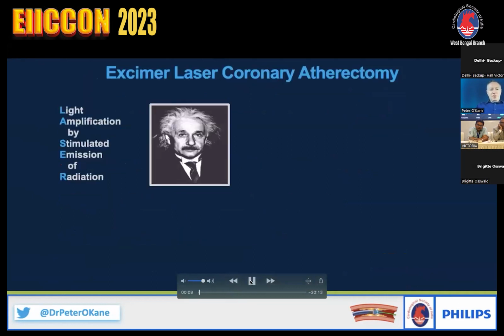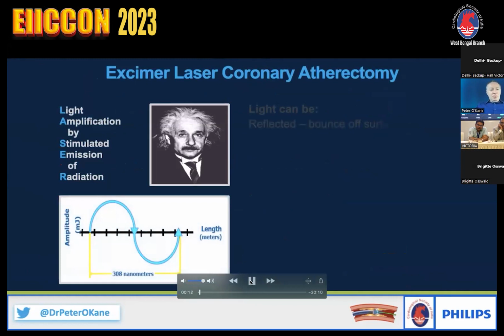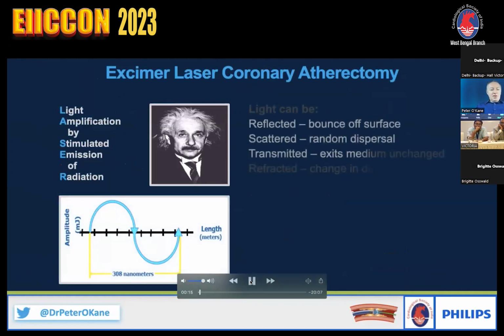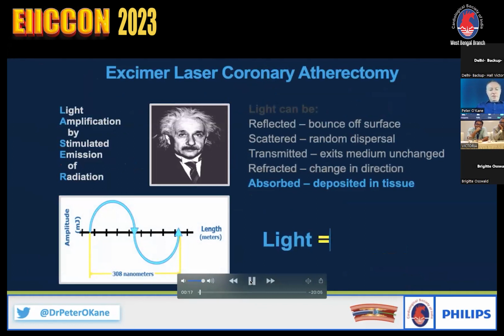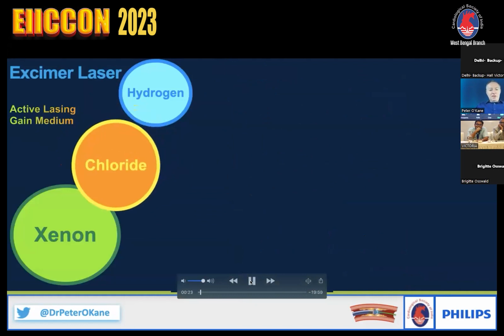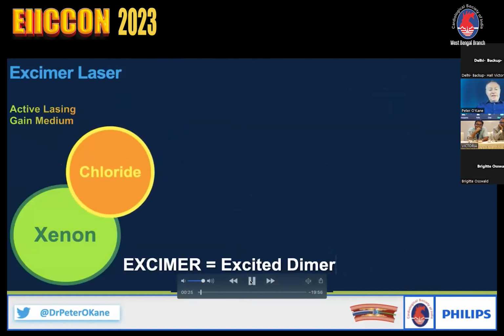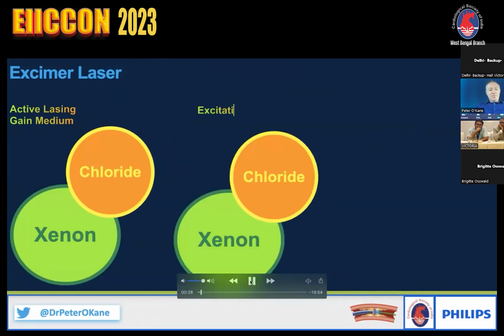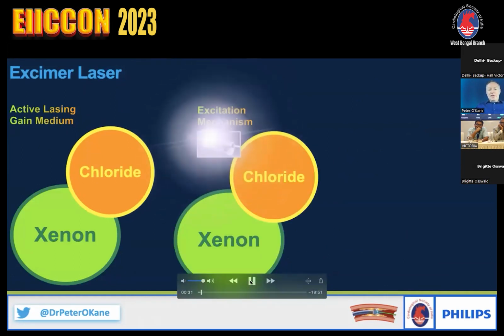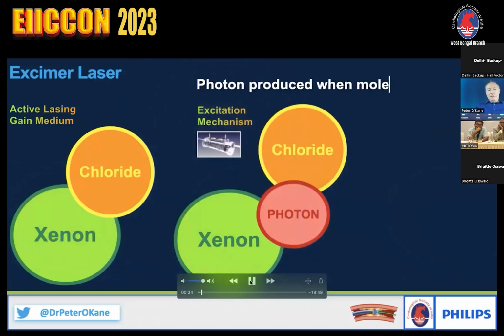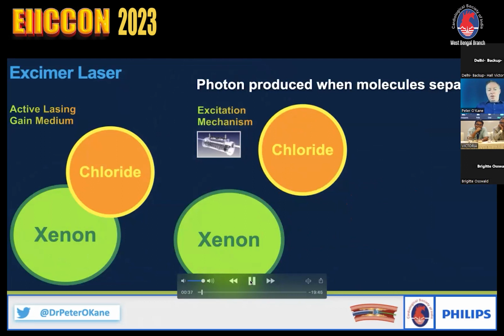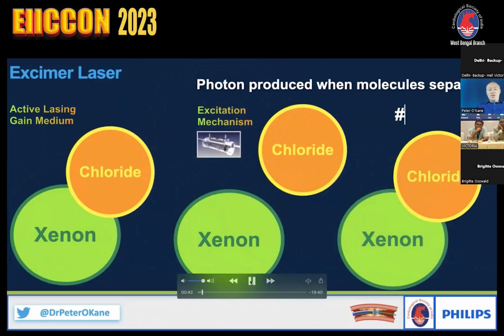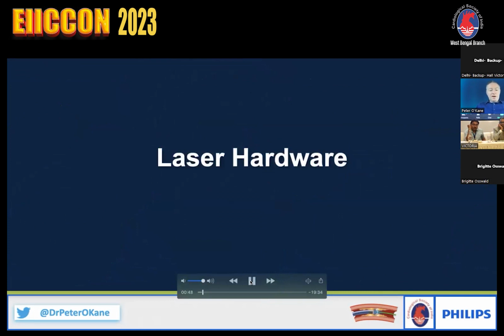So I'll just start really with talking about what laser is in principle. Light amplification by stimulated emission of radiation is the absorption of light that we're really interested in. As that gets absorbed into tissue, that energy is used to break down the material. Within the laser system, which Philips is the only FDA approved one, we have the xenon chloride gas, an excitation mechanism, which is electricity, pulls those molecules apart, produces the photon, and that process is repeated continuously and allows us to generate this light energy. It's not just the light energy which we will use, as you'll find out as I go through.